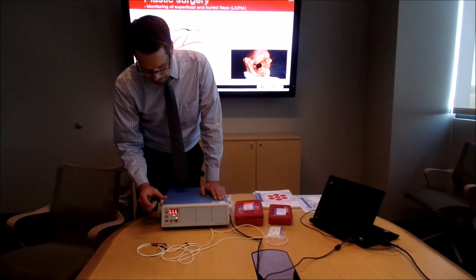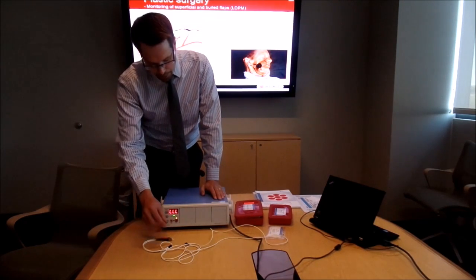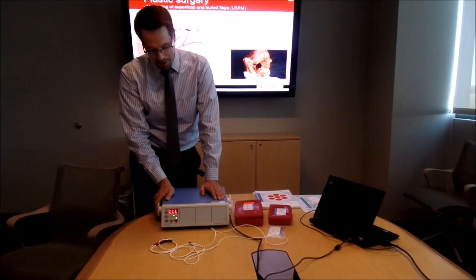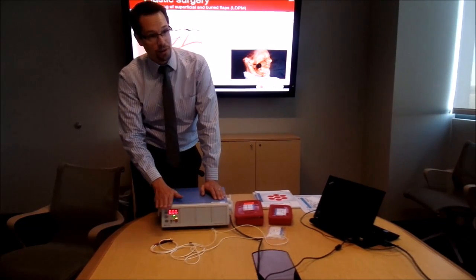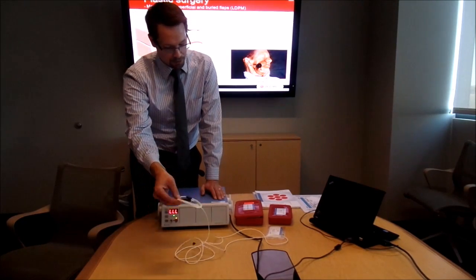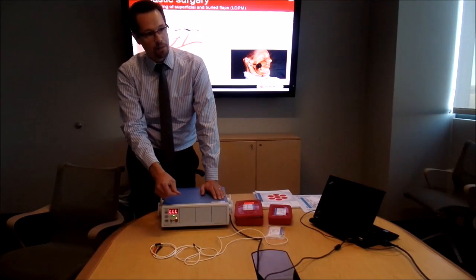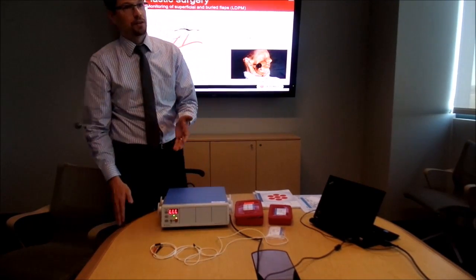Calibration button, this is what we have here on top. This is used to then calibrate the laser Doppler probes. I would recommend, if the opportunity is there, if you ever do swap probes to the same machines, you unplug this probe, maybe perhaps send it to be sterilized, plug a different probe in to then calibrate that probe at that time. You may see some optical differences from probe to probe, even if they are the same model.